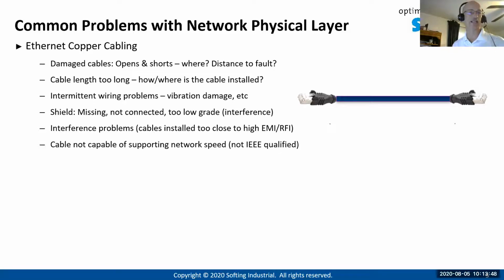One of the big trends these days is the issue of whether the cable can support the network speed. Networks are getting faster because it's not just sending messages between PLCs and devices - the network might be doing real-time vision systems, video monitoring, supporting wireless access points, or hybrid IT responsibilities. So the need for speed is there, and as network speeds increase, like putting in new switches, can that cable support it? It's much more than a question of electrical conductivity - it's about supporting the high frequencies.